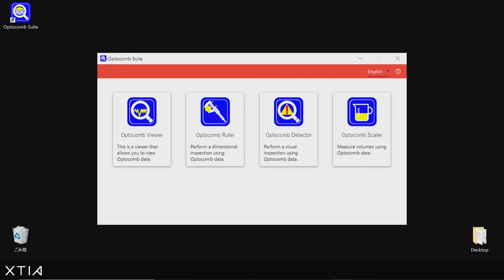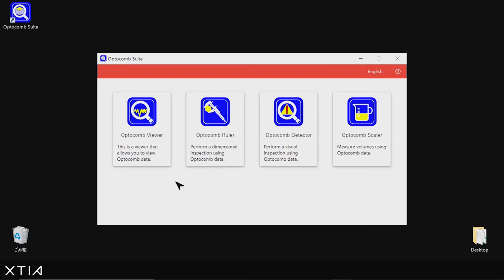From this Optocomb Suite portal, you can select your preferred language, so here Japanese or English, so let's keep going with English. And you can choose the toolbox you want to use first. In this first tutorial, we are going to focus on the Optocomb Viewer in order to visualize and measure features of a valve body.